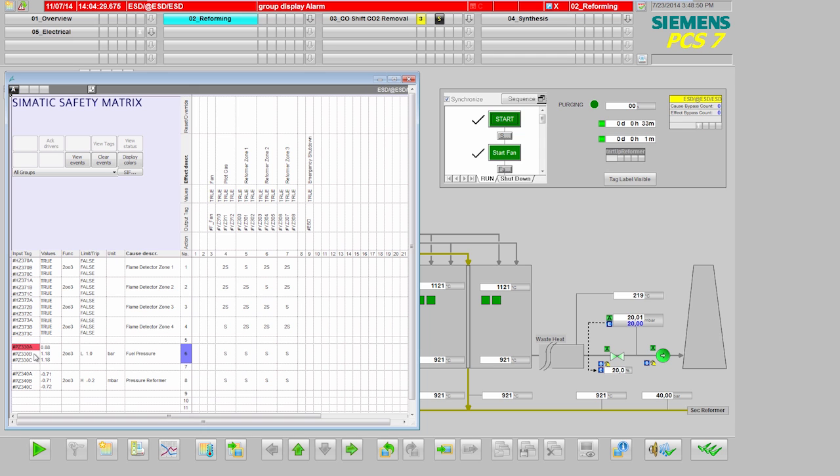If additionally a malfunction will occur at one of the other measuring points, the two of three requirement would no longer be met, thus closing the fuel infeed and shutting down this system component. It is therefore important to check the measuring point at which the fault has occurred as quickly as possible.